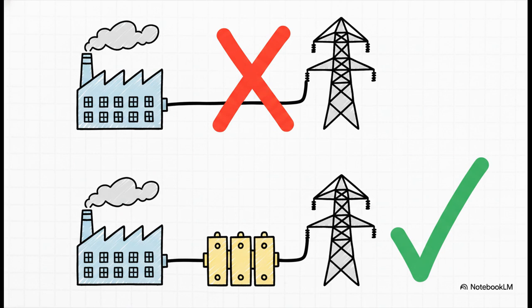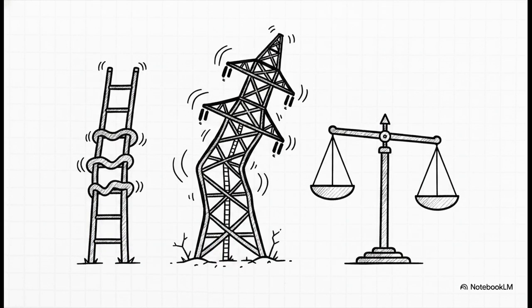This facility would literally just be actively wasting grid capacity. So they must physically install power factor correction capacitors to fix the electrical math at their own boundary before they ever get the green light. You can't just pay a fine and run inefficient equipment. It just doesn't work that way. So before this, you knew the voltage variation limits. Now you've got the power factor requirements locked in by installation type.